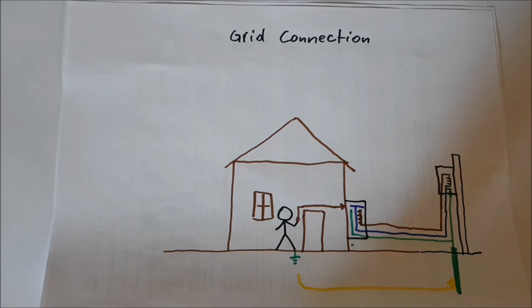So the next electrical circuit is our grid connection. This is what code is built on. Every grid connection comes with a transformer and a neutral to ground bonded end of the transformer coil, which is earthed there by an electrode at the source of power. This here would represent the TNS system, so we are getting line, neutral and earth supplied to our load center here.